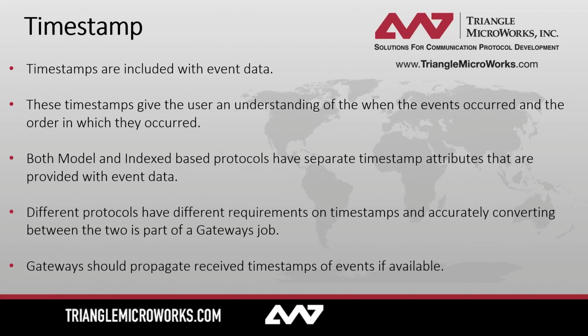Gateways should propagate the received timestamps if available, but one exception to this could be, think of a situation where you have a Modbus device and that information is being converted to DNP. Modbus doesn't have a concept of timestamps with its point, so the best the gateway can do in this situation is fill the time slot when reporting up to the DNP with the time that it received the data from the Modbus device, rather than the timestamp from the Modbus device, which wasn't available.